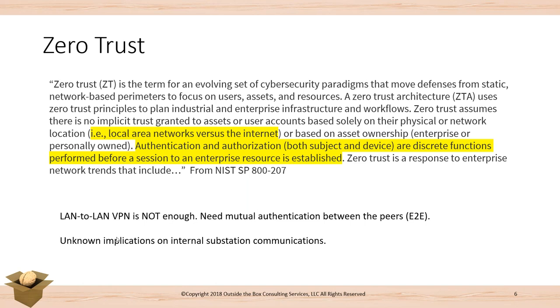There's also a lot of discussion in the industry about what's called zero trust, which requires end-to-end authorization regardless of if you're on the same network or not. This is from NIST 800-207, and NERC is actively discussing this concept for potentially future versions of NERC CIP. This kind of emphasizes that LAN-to-LAN VPNs are not enough — if you go to zero trust, you need mutual authentication end-to-end between the peers. Routable GOOSE, Routable Sample Values, and Secure Layer 2 GOOSE and Layer 2 Sample Values are really structured and set up to support the concept of zero trust.